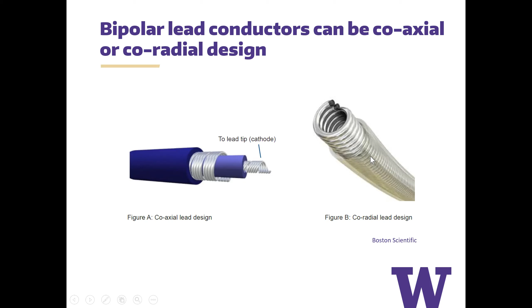The other design is the co-radial lead design, in which there are 2 wires, and you can see that they wrap into this coil simultaneously. They're right next to each other, separated by a very thin polymer of insulation. The disadvantage is obviously that once the larger insulation breaks, both of these are jeopardized. But the advantage here is that you potentially have a smaller lead diameter.